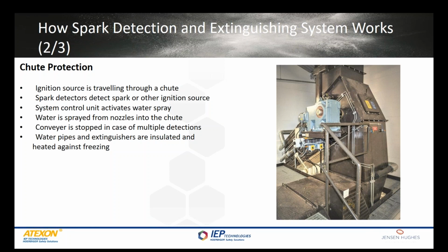This slide describes how to protect a chute between 2 conveyors. And basically, everything is the same as dust pipe protection. The most important difference is significantly lower material speed, which leads to shorter distance between spark detection and extinguishing points. Typical distance with dust pipe is something like 6 to 7 meters, but with chutes, the distance is typically only 1 to 2 meters. The other differences are number of needed detectors and water nozzles, because protection area is typically bigger with chutes and material flow is more dense.